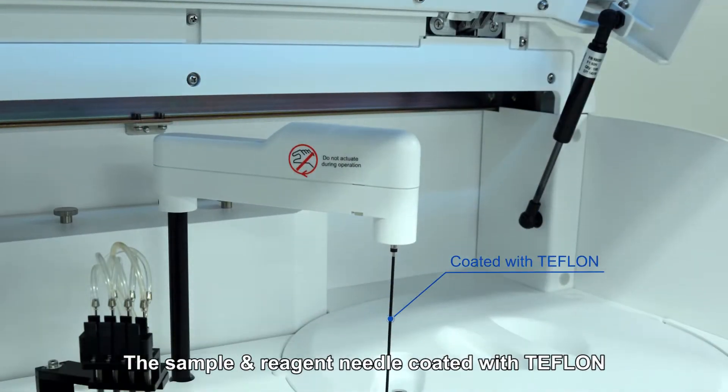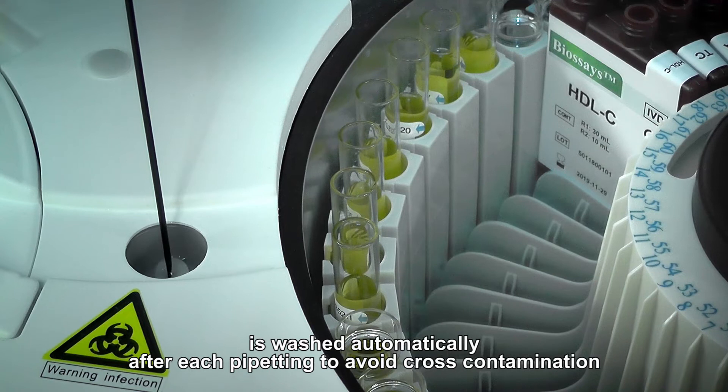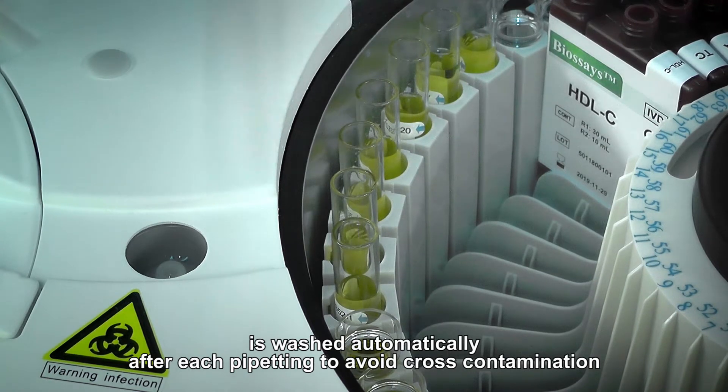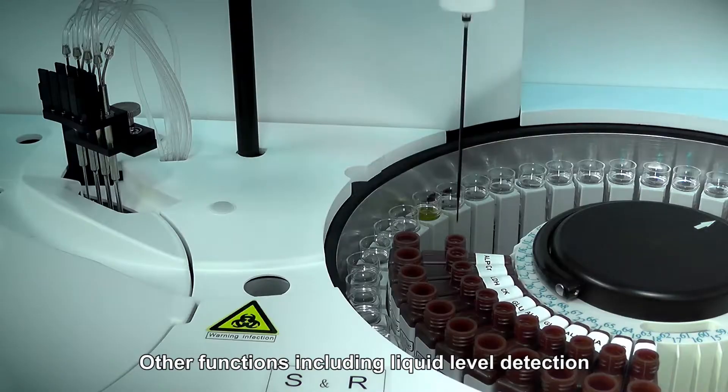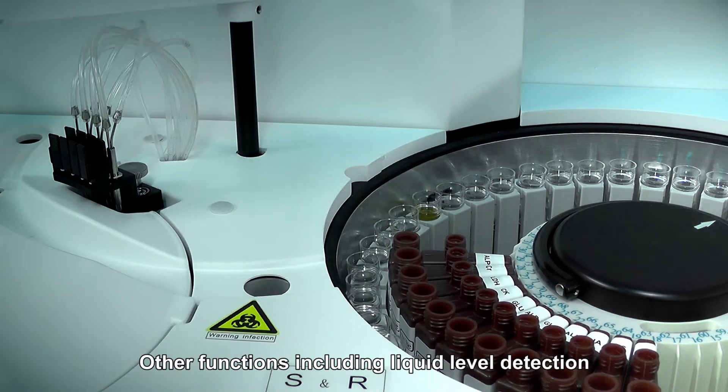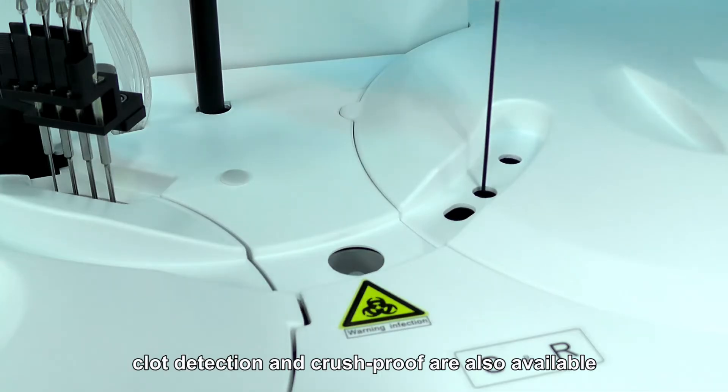The sample and reagent needle coated with Teflon is washed automatically after each pipetting to avoid cross-contamination. Other functions including liquid level detection, clot detection and crush-proof are also available.